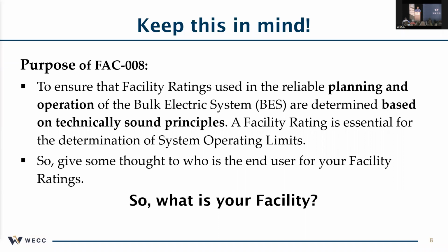FAC 8 already says to consider ambient conditions when you're doing your ratings. It doesn't say how often, but it says you can consider those ambient conditions. It already says you're supposed to address emergency ratings and normal ratings. So there's nothing in FAC 8 that prohibits you from modifying your methodologies to satisfy 881 for your tariff people.